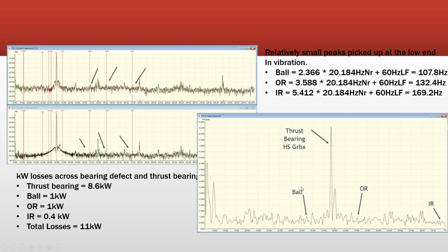There's the secret. So when I start taking a look at it, what's even cooler is everything on the powertrain side of that air gap, including the generator, all the multipliers translate backwards. So they translate to that RPM. So I'm not hunting for RPMs; it just translates backwards. We actually figured that out when testing active front end drives, being able to test through those variable frequency drives because they don't have a DC bus, the translation backwards. We're publishing a paper on that next year.